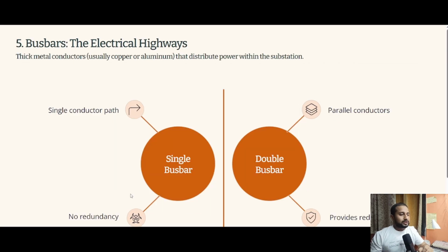The next important equipment are the bus bars. They are also known as electrical highways. They are nothing but thick metal conductors, usually copper or aluminum, that distribute power within the substation. So there can be two types of bus bar arrangement. That can be single bus bar system or double bus bar system.